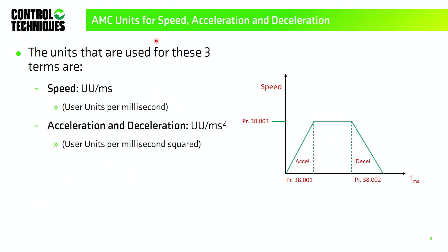The units for menu 38: speed is in user units per millisecond, shown on the Y-axis. Accel and decel are in user units per millisecond squared. While these are unusual terms, they're engineering units, so I don't have to convert from degrees per minute or RPM and time — they're already in engineering terms, which makes calculating them easier.